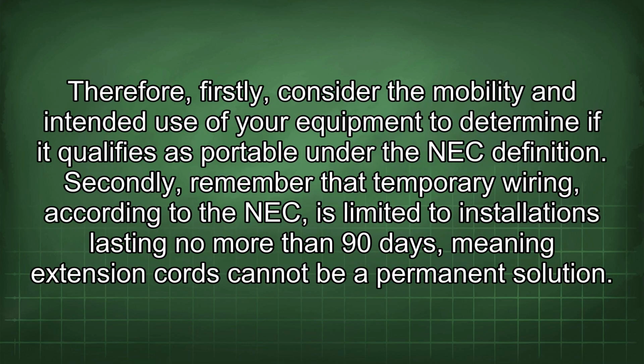Therefore, firstly, consider the mobility and intended use of your equipment to determine if it qualifies as portable under the NEC definition. Secondly, remember that temporary wiring, according to the NEC, is limited to installations lasting no more than 90 days, meaning extension cords cannot be a permanent solution.